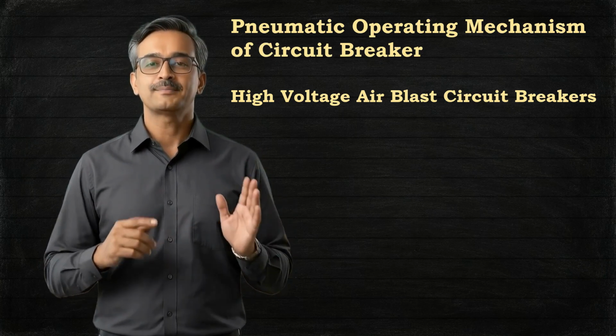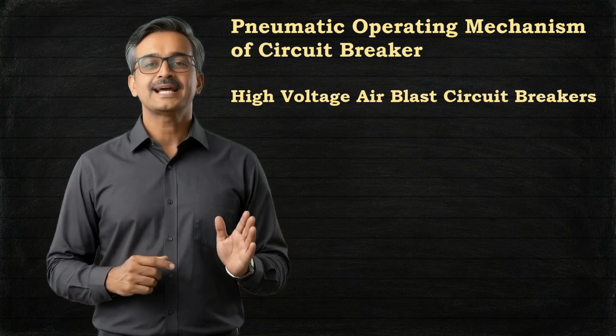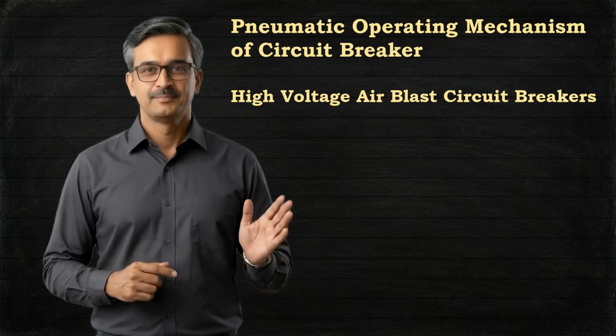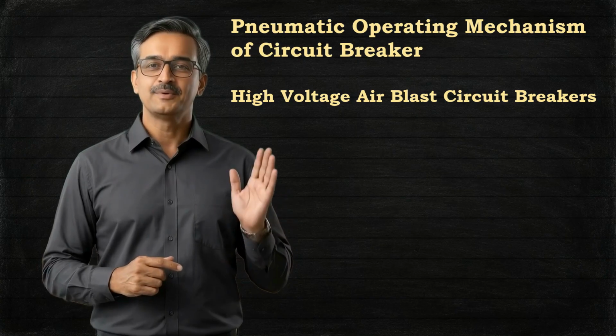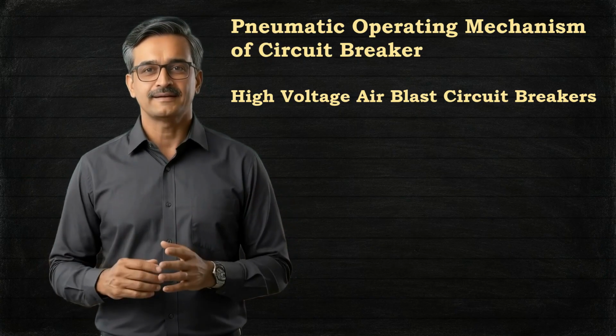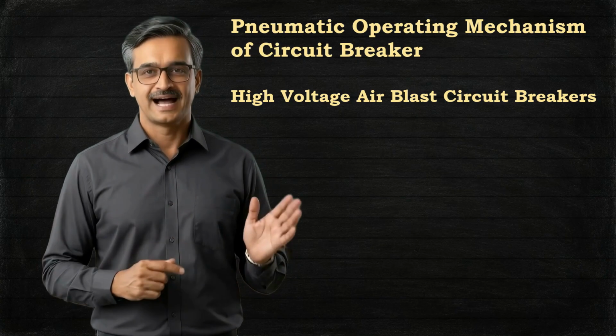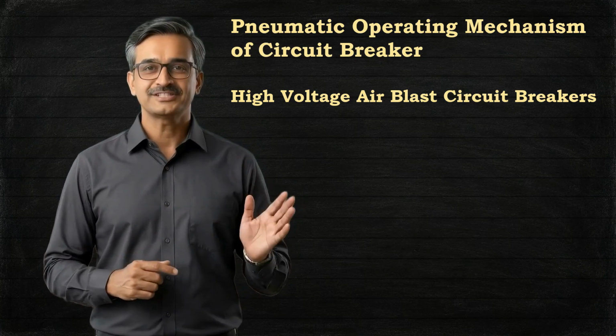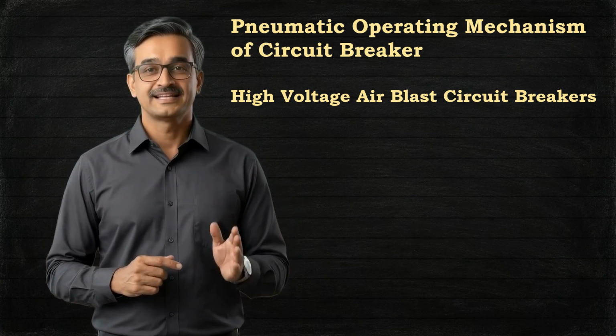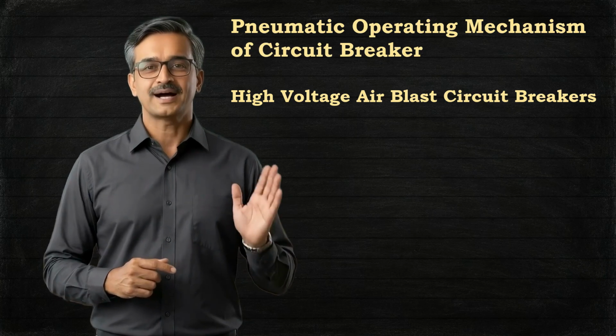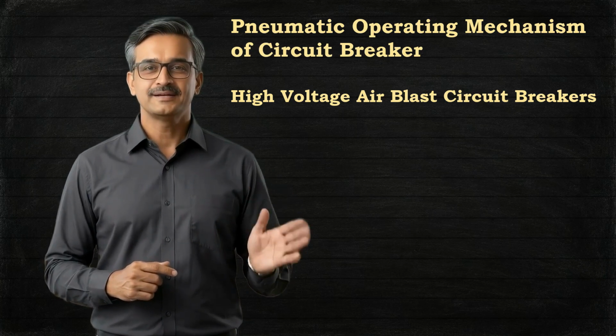To open the circuit breaker, the same compressed air is used. The compressed air entering the arcing chamber produces high pressure, which pushes the moving contact back and thereby opens the circuit breaker. At the same time, the forceful blast of air quenches the arc.